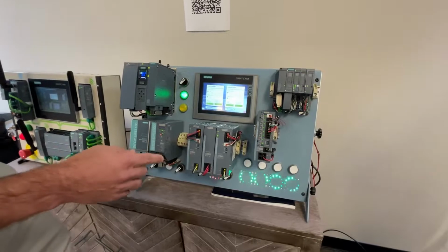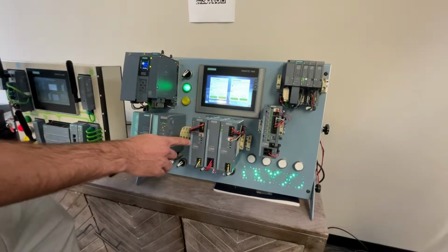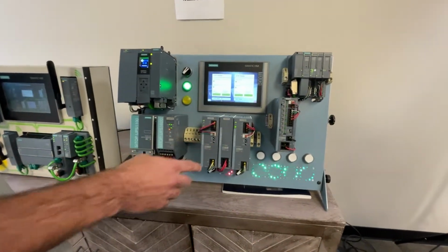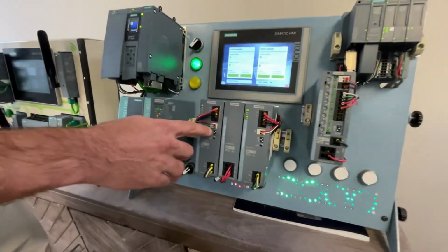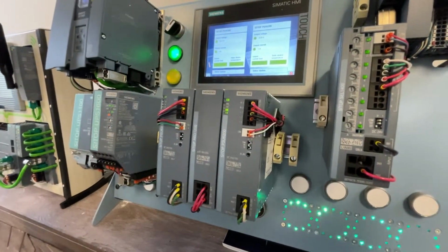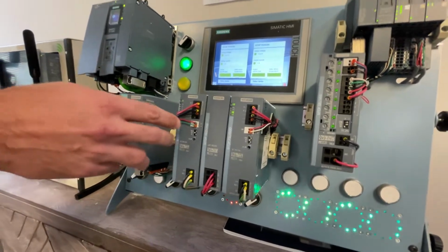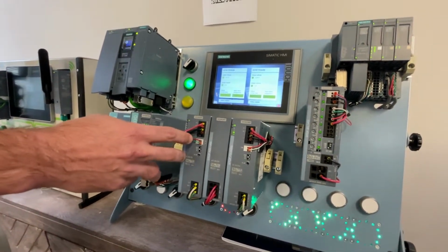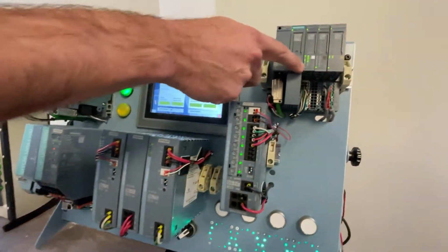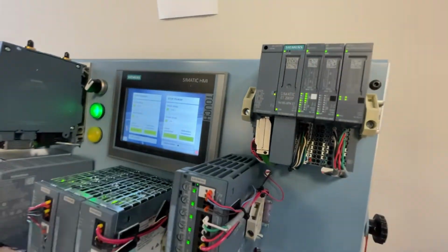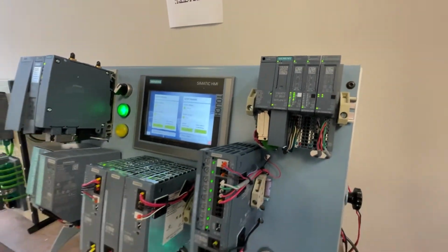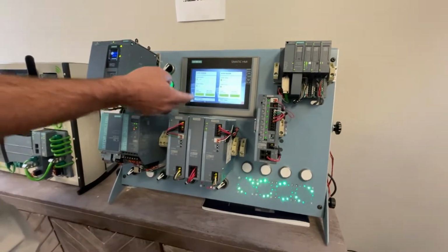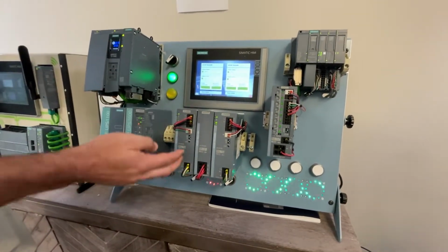So our newest power supply line we call the Sitop PSU 6200 supply. You'll notice that there are these two white ports coming out. And these two white ports are a diagnostics interface, and basically it's a serial output, digital output signal that's going into the I/O block. So you see the flashing LEDs. And with this information, with the function block programmed to the PLC and of course the faceplates, you can actually get more diagnostics out of the standard power supply.